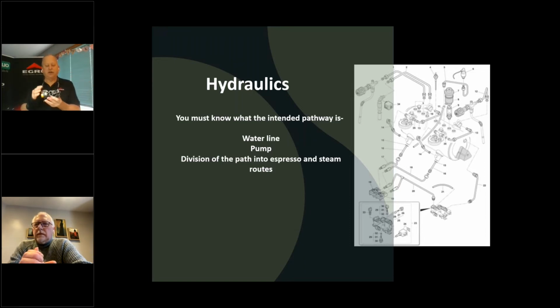An expansion valve, once again: once you go past the check valve, you've entered into the espresso world. As you heat the water in that closed system of the espresso, you can build 300, 400, 500 pounds of pressure. That'll actually start cracking pipes, fatiguing them, if it's not opening at the right level. Typically they're set to 12 bar, just the way they come from the factory. Some are adjustable, and I venture to say that most are maladjusted. That expansion valve just pops open when you hit 12 bar and exhausts a little bit of pressure. And by the way, on an expansion valve you are only looking at a drip. You should never see running water.